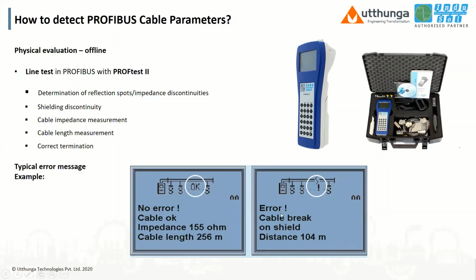You can see one example here. Error: cable break on shield. Distance is 104 meters. That is, this cable break has happened at 104 meters. Then the maintenance guys can go directly to 104 meters and find out what the error in the plant is. And also you can log the data here and print it out through a PC. That's also possible.